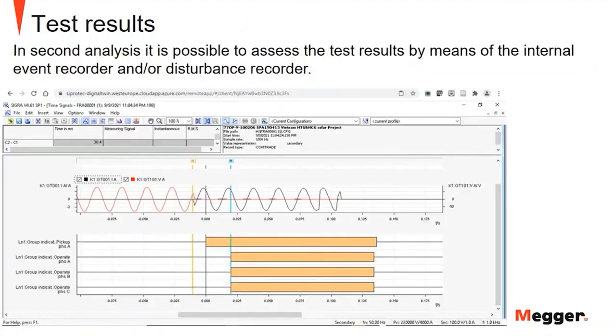In second analysis, it's possible to assess the results by looking into the disturbance recorder or event recorder generated by the protection relay after the injection of the fault or the test injection. In this case, you can see that we can measure then. This ComTrade file is coming from the relay, and the fault started here. Voltage goes down, current goes up, fault starts here. After this time, we have a general start, and the trip is here, and we have the trip after 30 milliseconds.